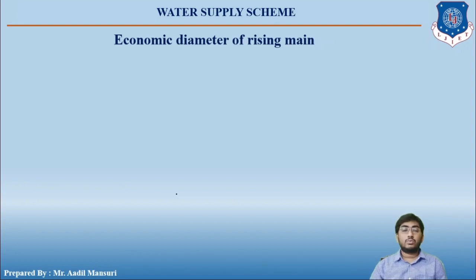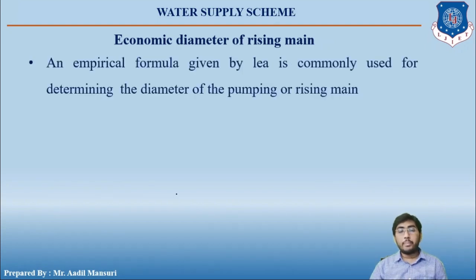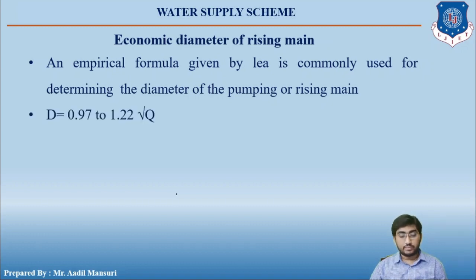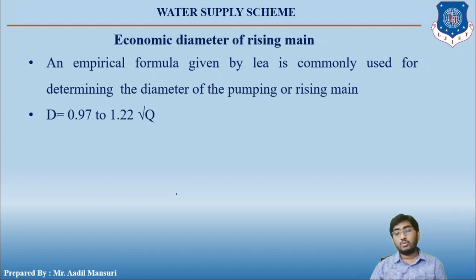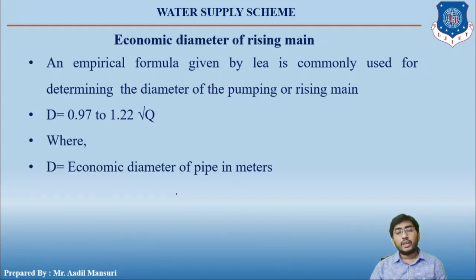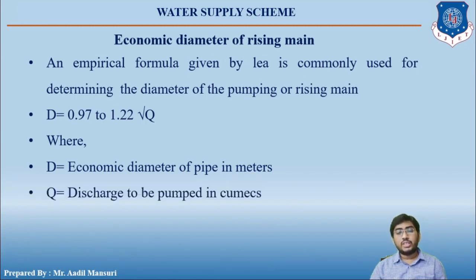For optimum efficiency, it is necessary to design the diameter of the pumping main so that the overall cost — both initial and maintenance — is economical. The diameter that provides this optimum condition is known as the economic diameter. An empirical formula given by Lee is commonly used: d = 0.97 to 1.22 × √Q, where d is the economic diameter in meters and Q is the discharge in m³/s.